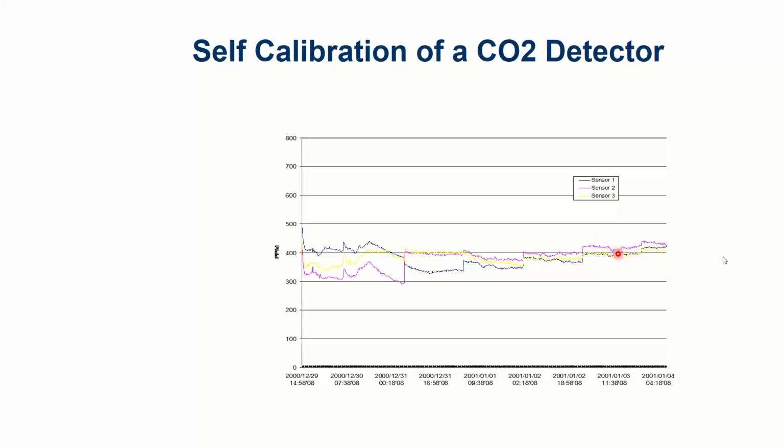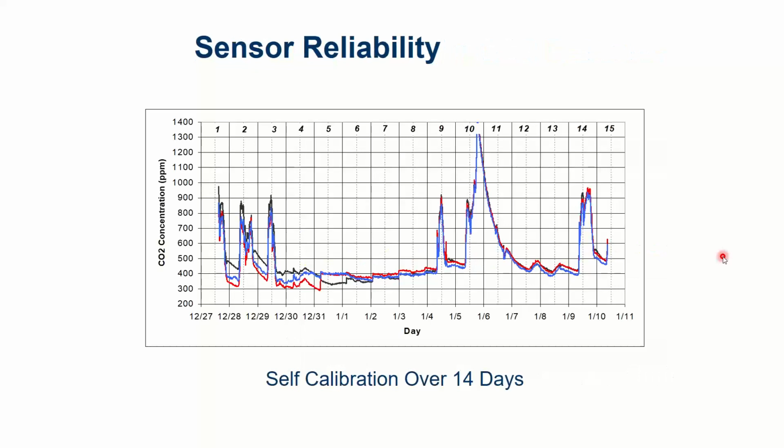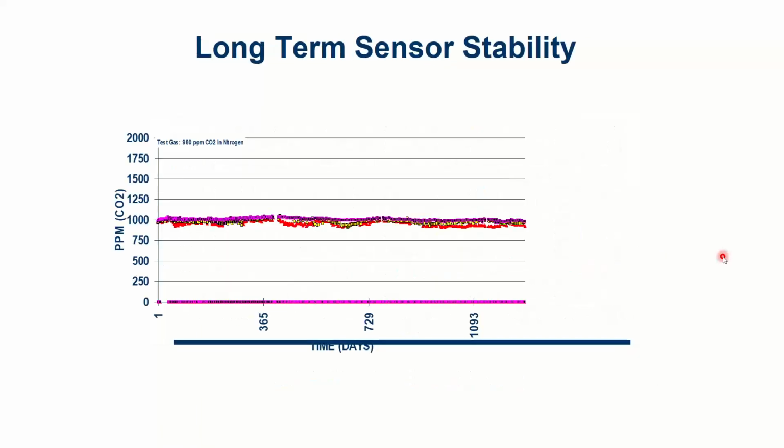which is basically the same number in terms of this horseshoe hand grenade type measurement. Here's 3 sensors over 2 weeks. Here's 3 sensors over 3 years. In this case, with a certain known CO2 concentration in a chamber, and watching them keep constantly calibrating themselves back to baseline with each other. So it has become significantly more reliable, which helps a lot.